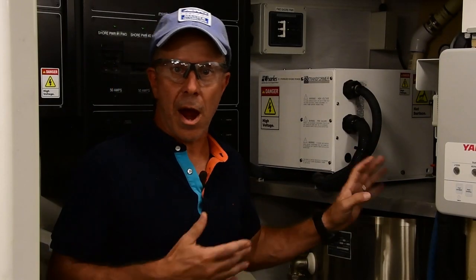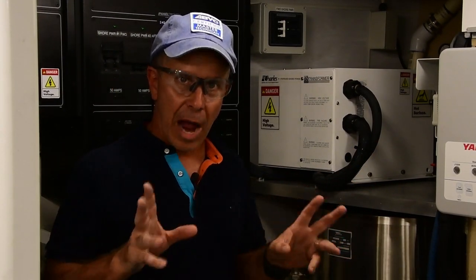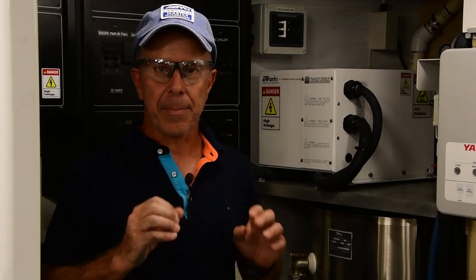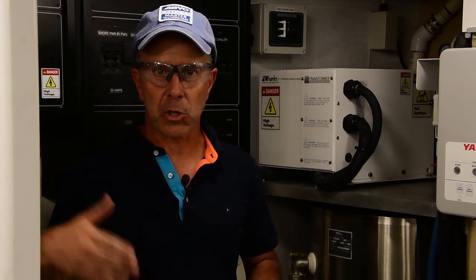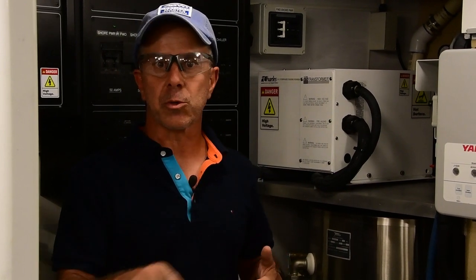Now, if you wire the shore power transformer for isolation mode, it means there's no connection between the dock or shore ground and the vessel's ground, and it's being done safely. Once again, because this transformer has now become a source of power, the ground can originate inside the transformer. All faults will travel back to the transformer and ideally trip a circuit breaker, rendering them safe.